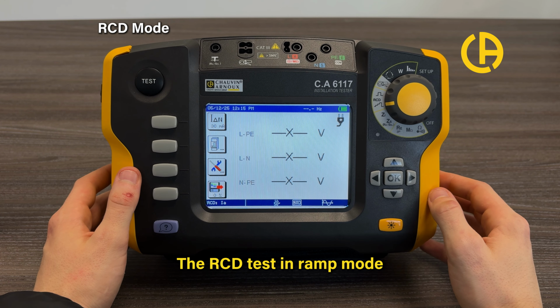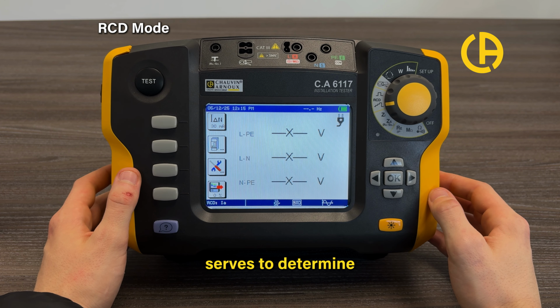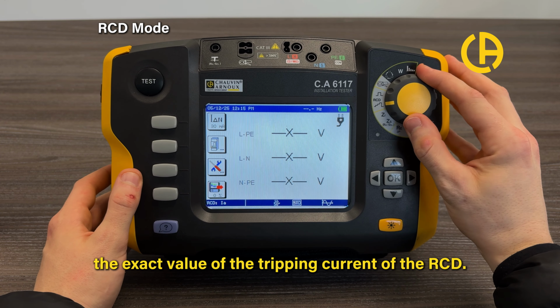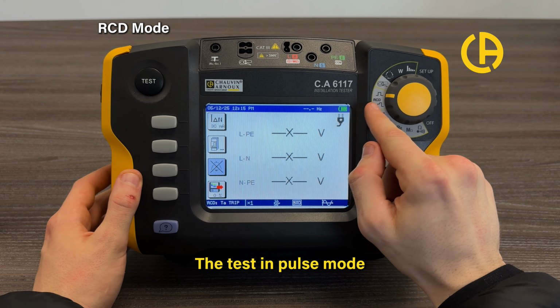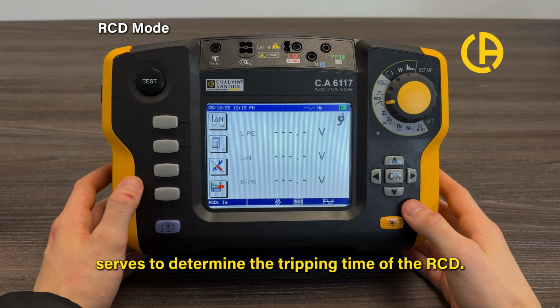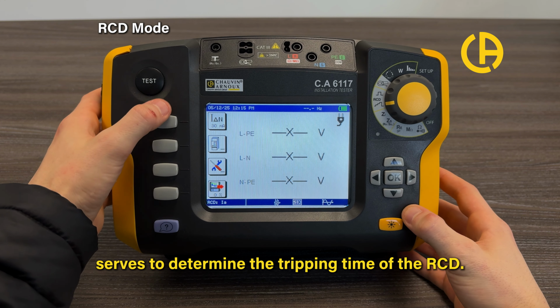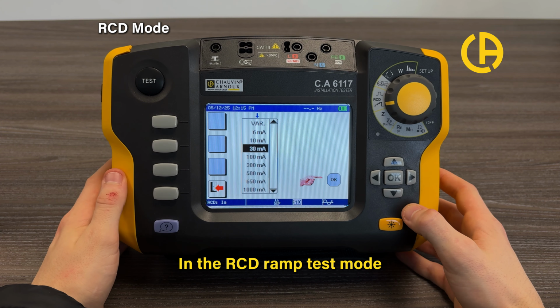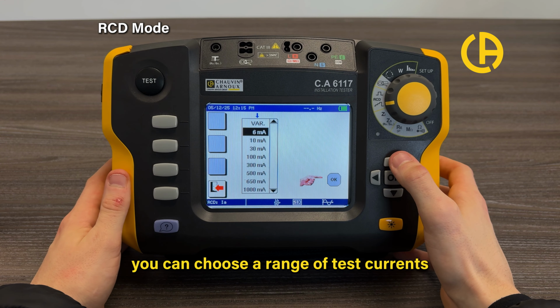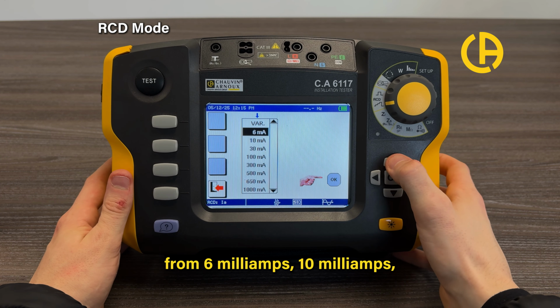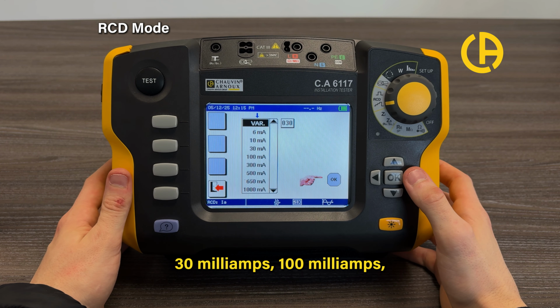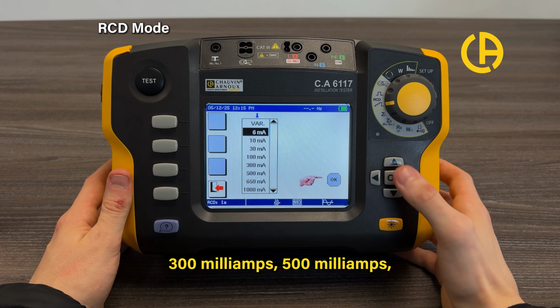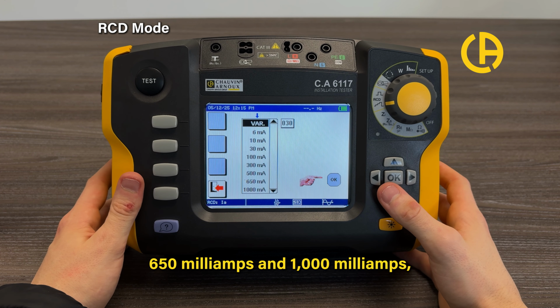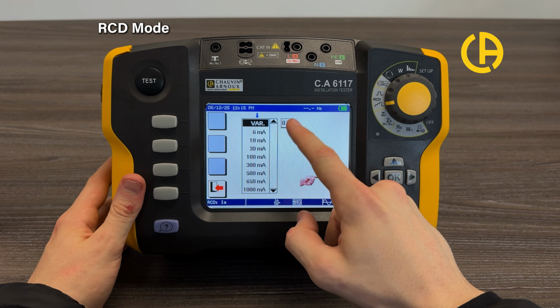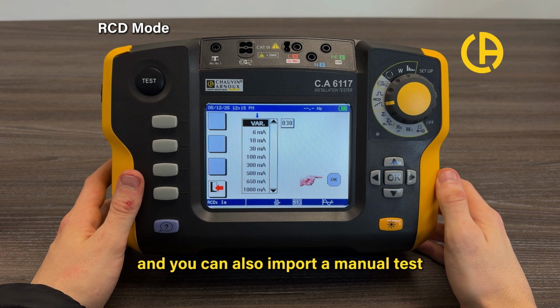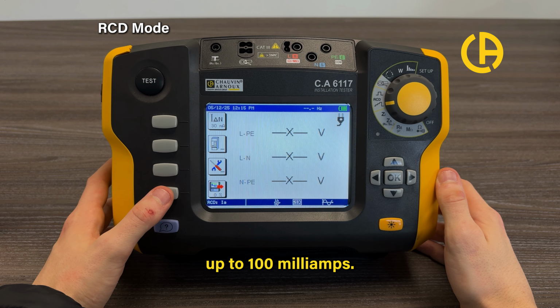The RCD test in ramp mode serves to determine the exact value of the tripping current of the RCD. The test in pulse mode serves to determine the tripping time of the RCD. In the RCD ramp test mode, you can choose a range of test currents from 6 milliamps, 10 milliamps, 30 milliamps, 100 milliamps, 300 milliamps, 500 milliamps, 650 milliamps, and 1000 milliamps. And you can also input a manual test up to 100 milliamps.